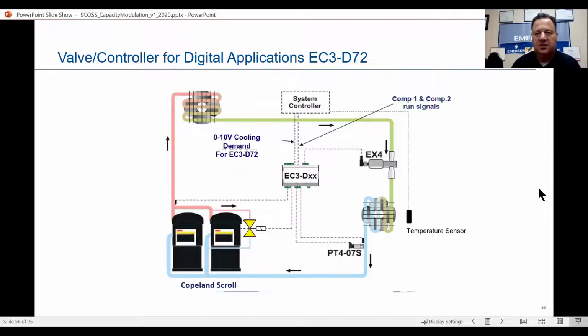All right, so let's see how this all works together. We've got the valve controller for the digital application, the EC3-D72. I'll try not to butcher this for you. So our controller's dead center here, coming back from the EC3-DXX, in other words, back to the system controller. Remember, this is an open loop. We've got compressor 1 and compressor 2 run signals, okay?